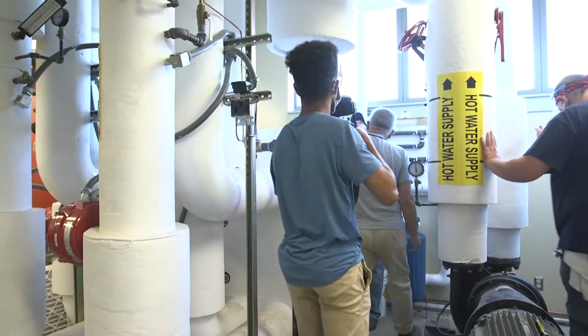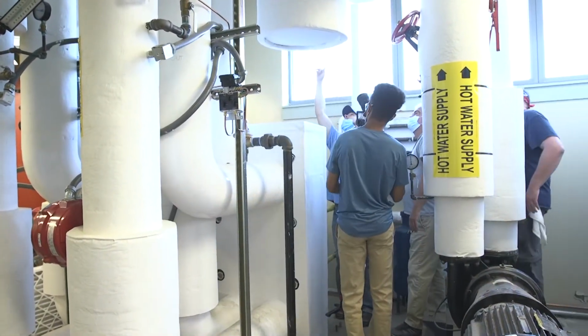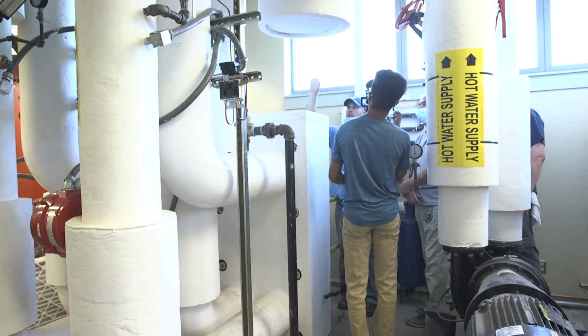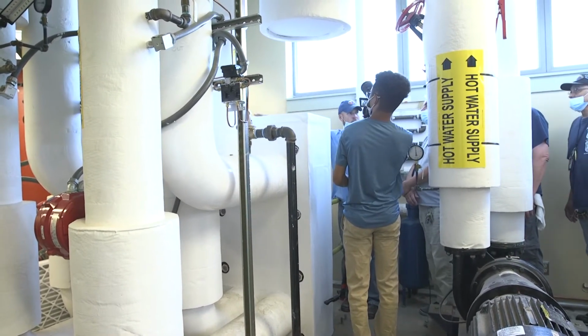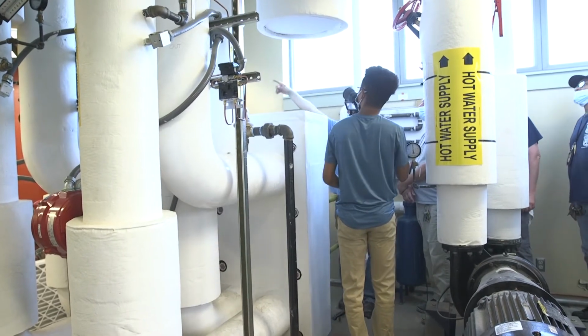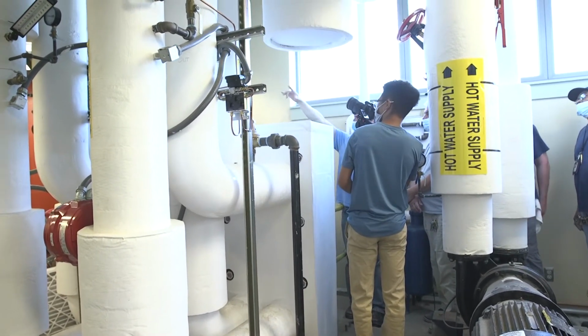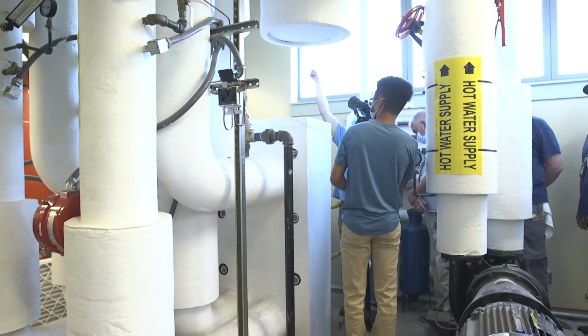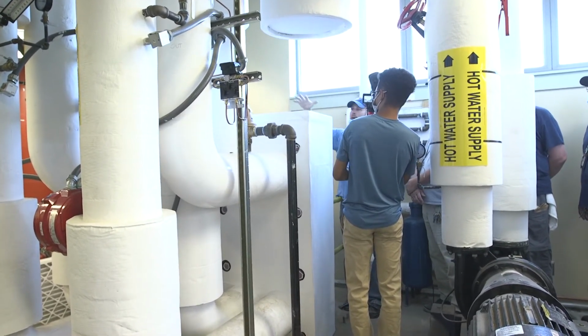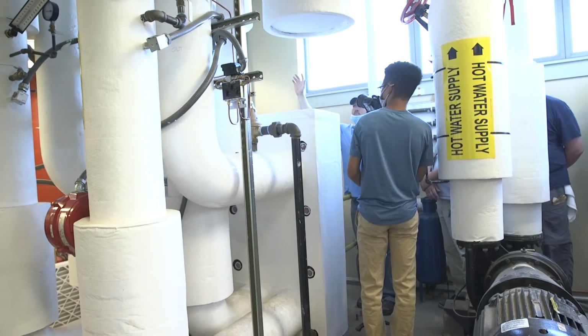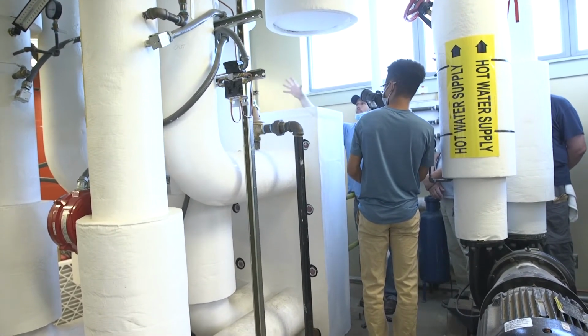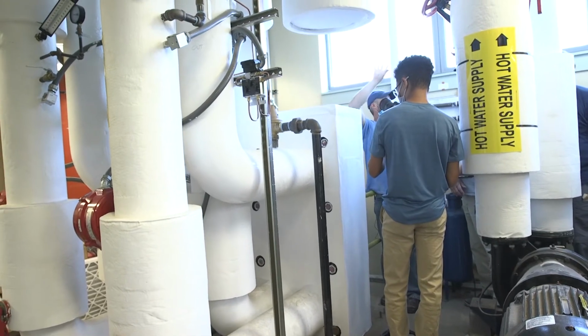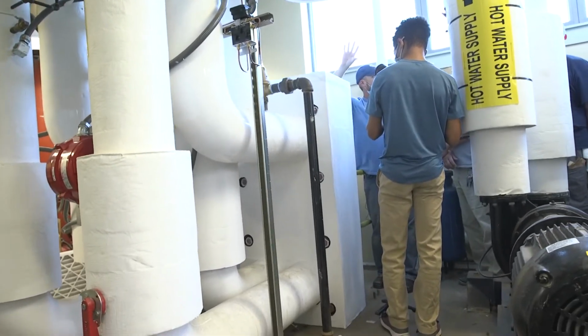you have this manual bypass where these two valves are closed. If you had a problem with these heat exchangers, or these heat exchangers had to be offline, you would close these valves on the pumps and open up these two valves, and you would be bypassing these heat exchangers. So your primary hot water would go past these heat exchangers and go right through the building system. But if we have a two heat exchanger setup, for example, we may keep one on and one on bypass. No, it's a one heat exchanger. It would bypass both of these.